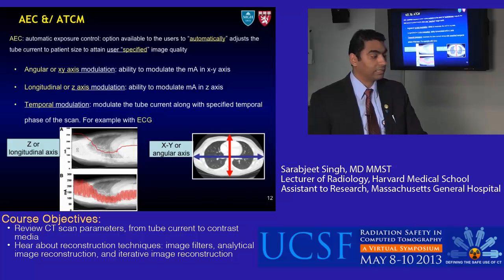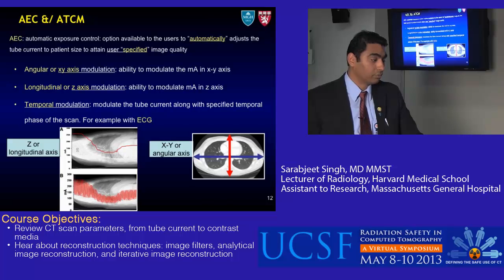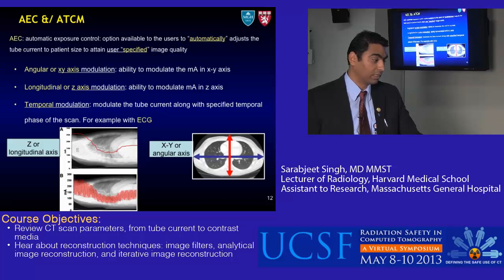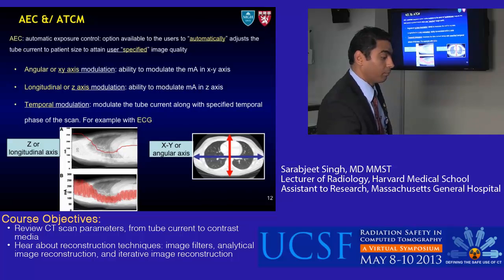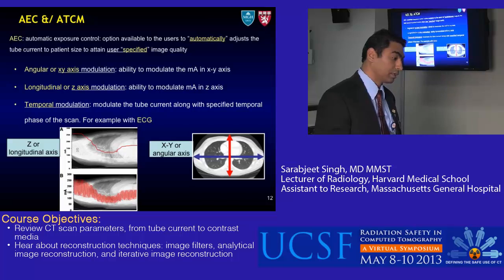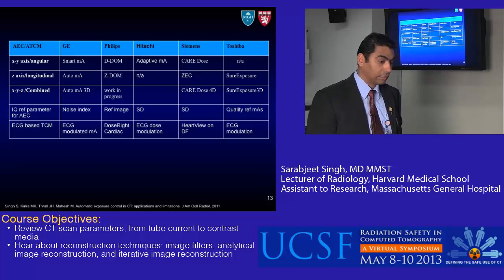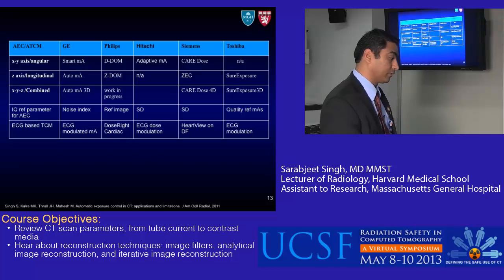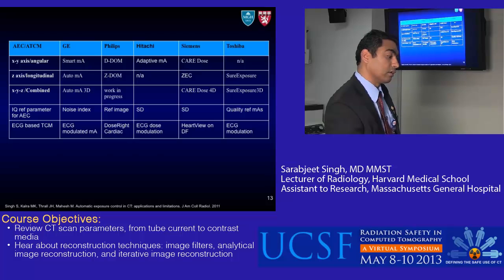Next is AEC, or ATCM — automatic exposure control or automatic tube current modulation. This is an option available to users to automatically adjust the tube current to patient size to attain a user-specified image quality. There are different types of ATCM: angular or XY modulation, which modulates mA in the XY direction; longitudinal or Z-axis modulation along the patient's z-axis; and temporal modulation where mA is modulated based on the phase of the scan, such as cardiac-based modulation via ECG. Plotting these parameters shows a lookup table comparing modulation types across vendors — for example, auto mA from GE is a longitudinal modulation, whereas Care Dose from Siemens is XY modulation.